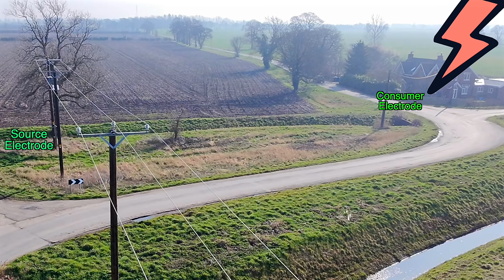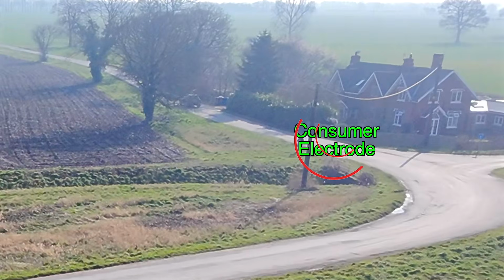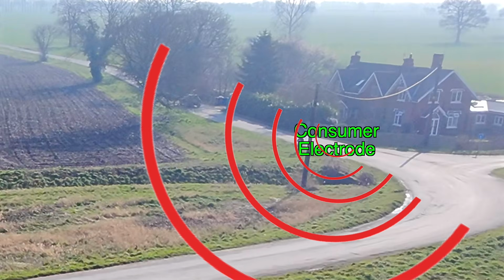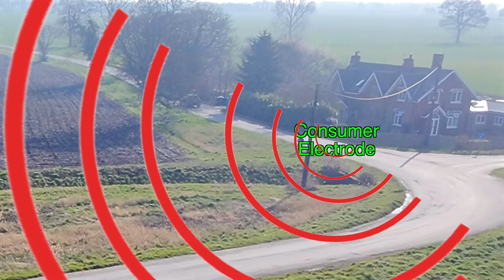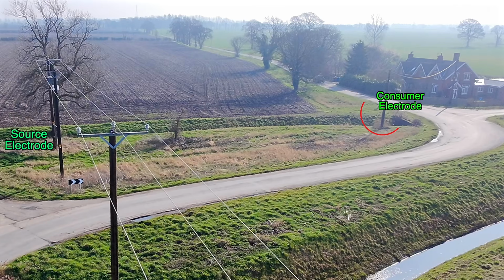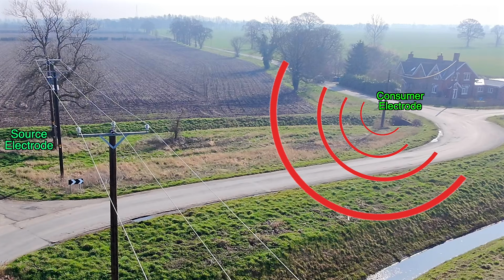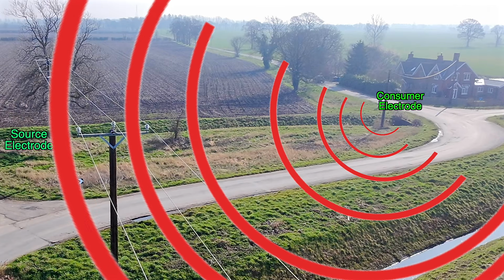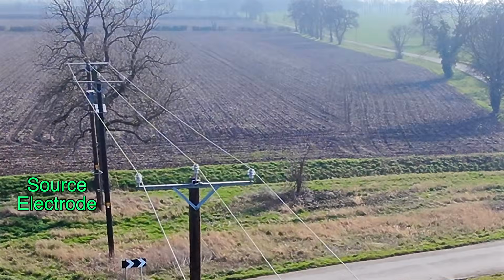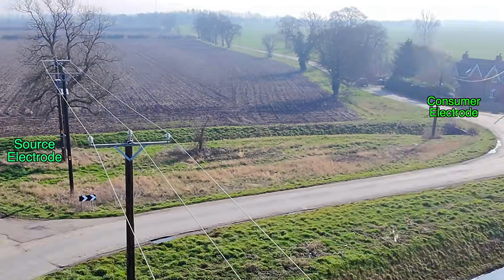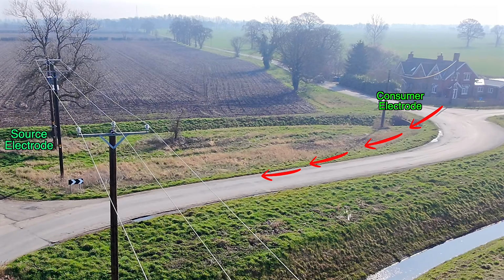When a fault occurs in a TT system, current leaves the installation through the earth electrode. It does not vanish into the ground, instead it spreads out through the soil around the electrode. Think of it like ripples in a pond. The current spreads out in all directions through the surrounding earth. Eventually, the fault current is picked up by the source earth at the transformer or substation. From there, the fault path continues back through the supply network, and finally, back along the line conductor. If everything is working as it should, the process allows the protective device to disconnect the supply automatically. So the ground is part of the fault path.